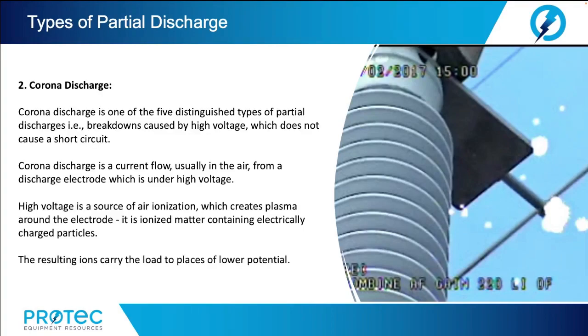The discharge is invisible in daylight, as most of the radiation generated is in the ultraviolet range, invisible to the human eye, and therefore the development of ultraviolet radiation detectors becomes a valuable complement to acoustic-based detection methods. In addition to corona discharge, the least harmful of partial discharges, there are surface discharges, related mainly to contaminated insulator surfaces, and internal discharges caused by degradation of internal insulation.